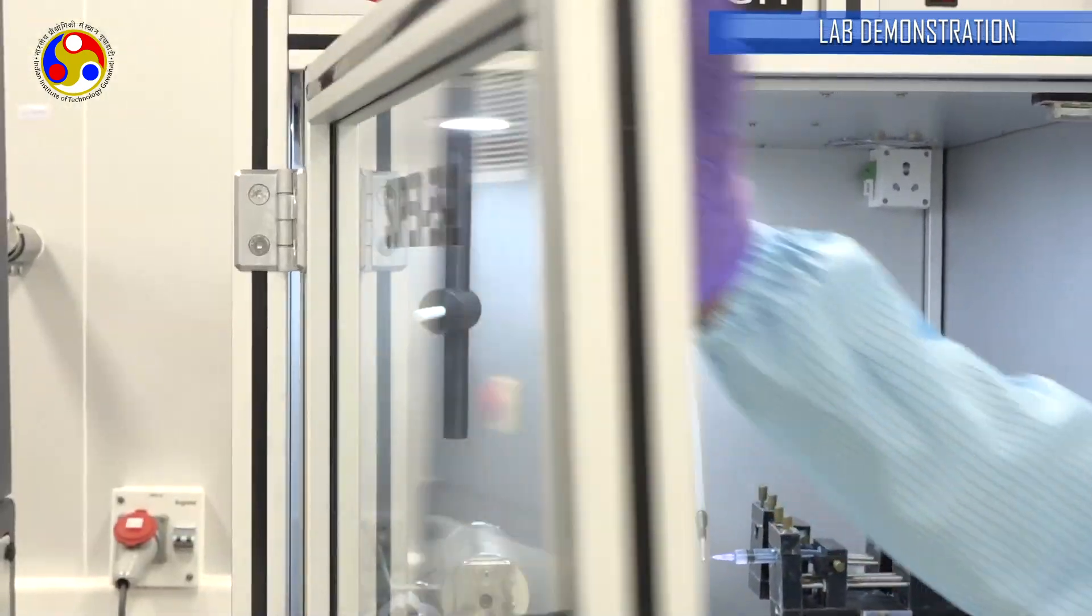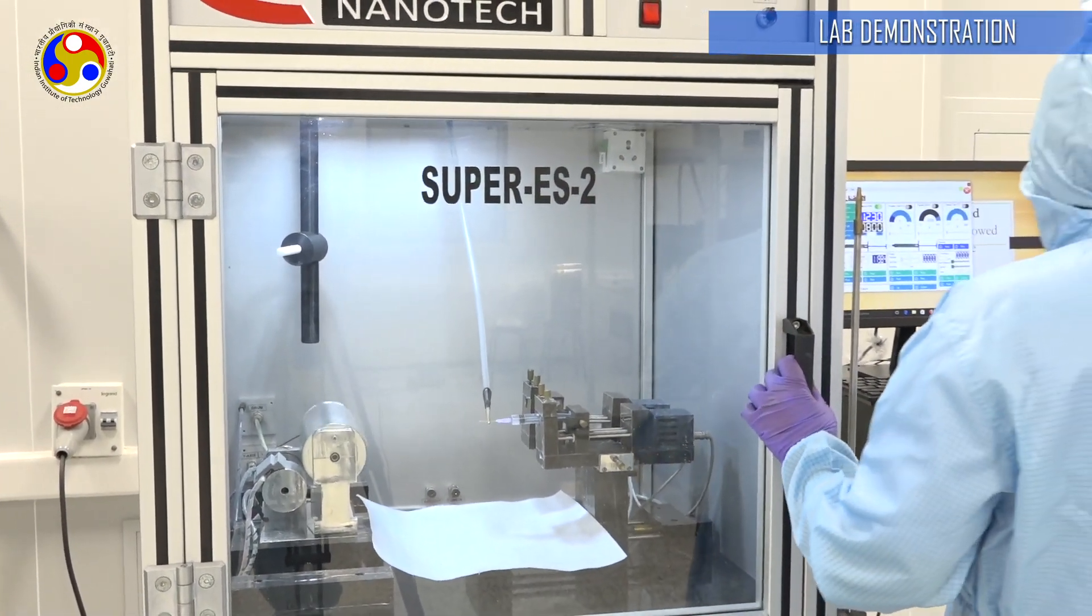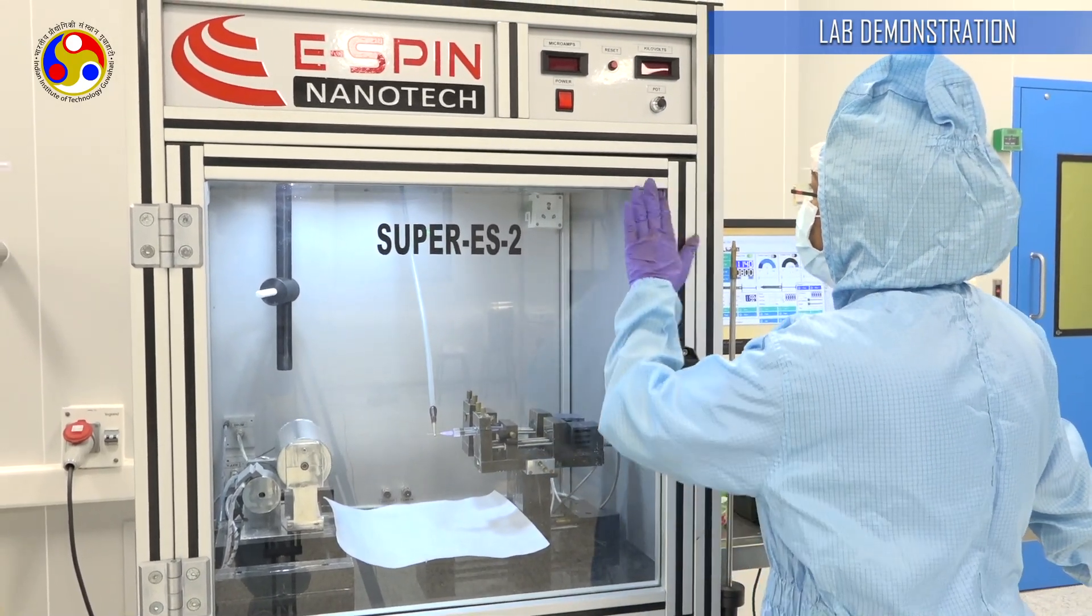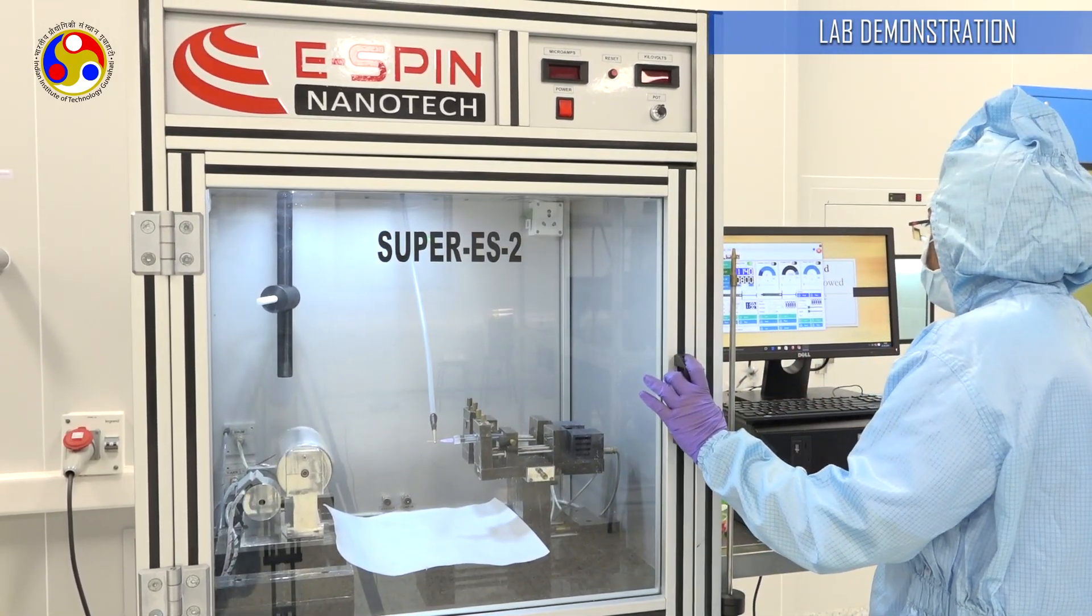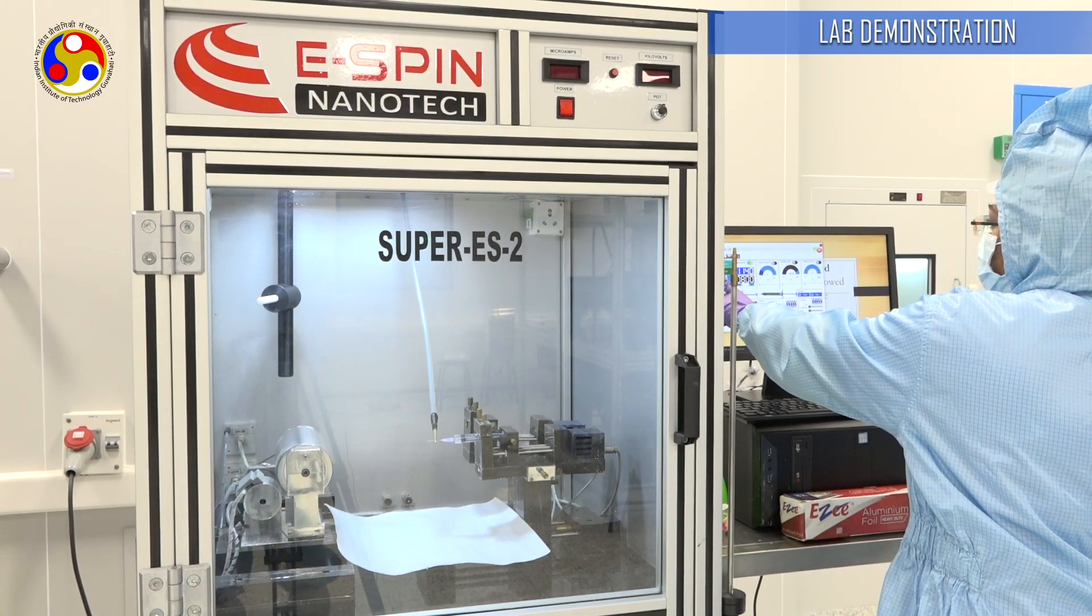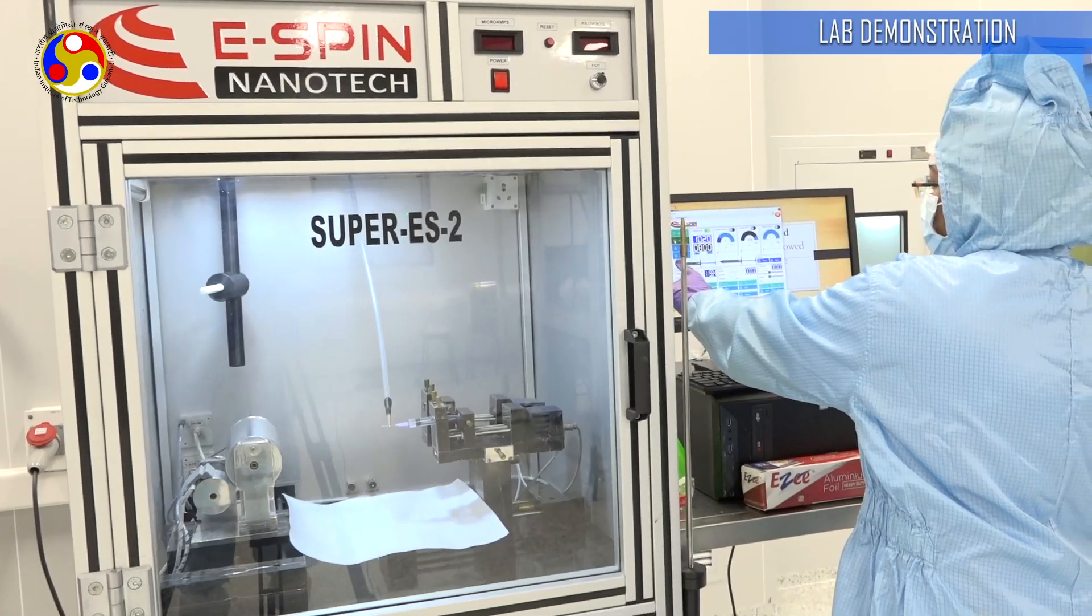Very importantly, I first need to close the chamber door before I turn this on. Since we are going to be using very high voltage, it's important to maintain the safety precautions. Right now at this software interface, it's showing HV off. I am just going to turn it on now.